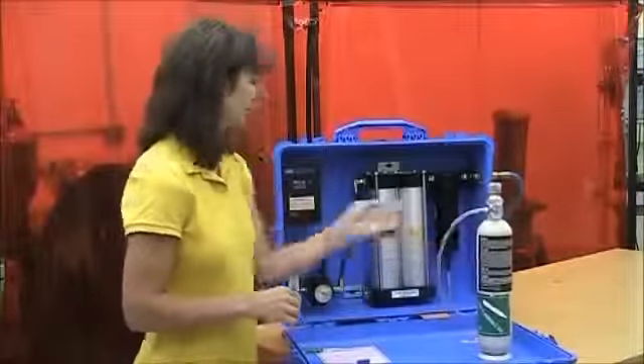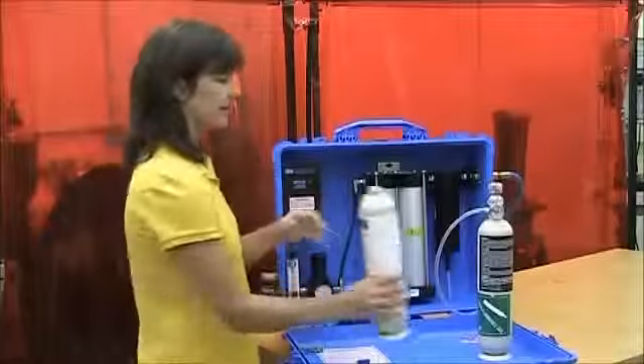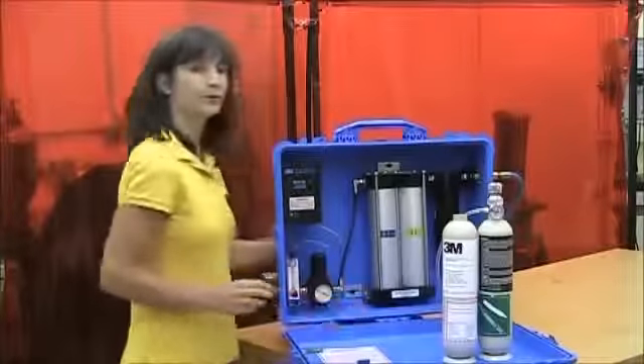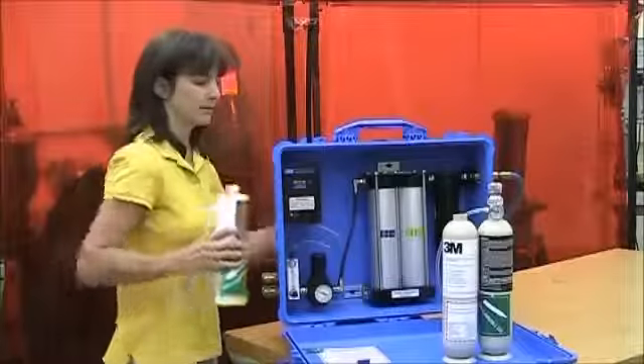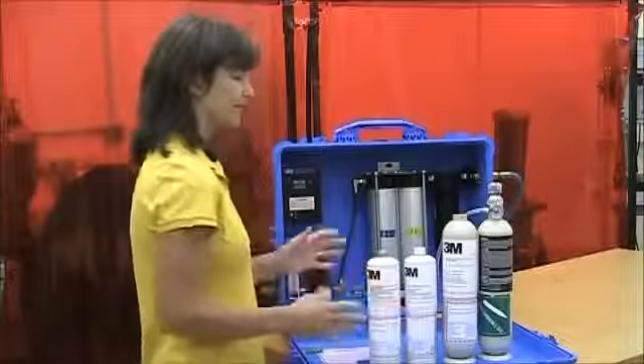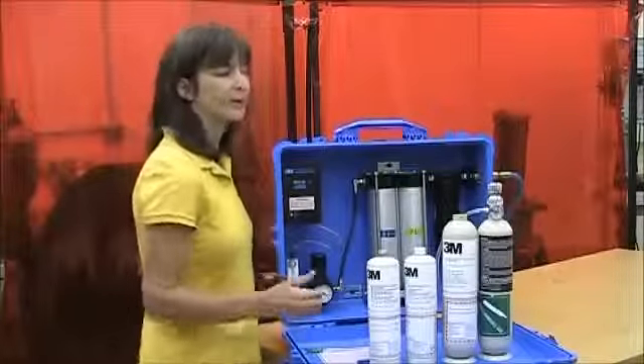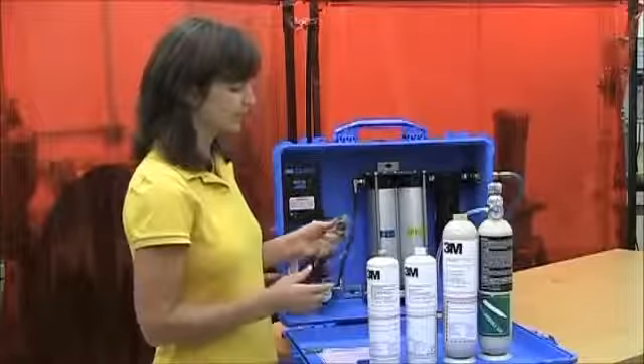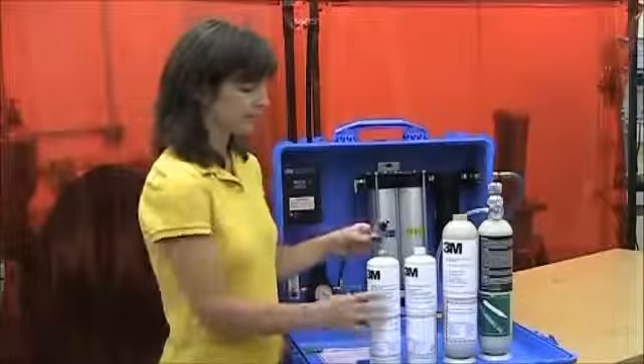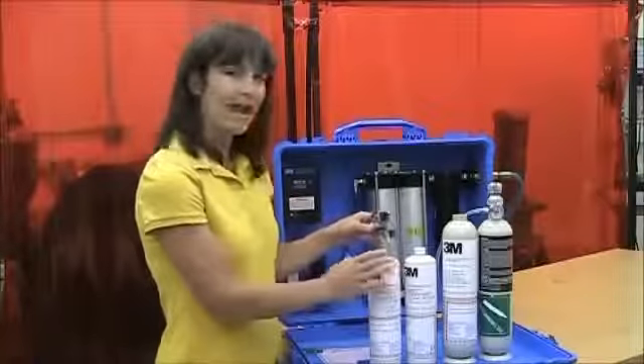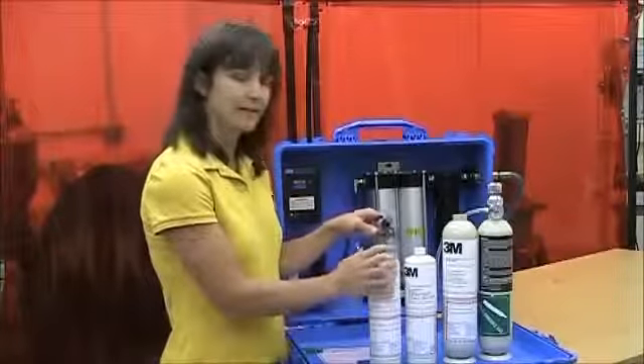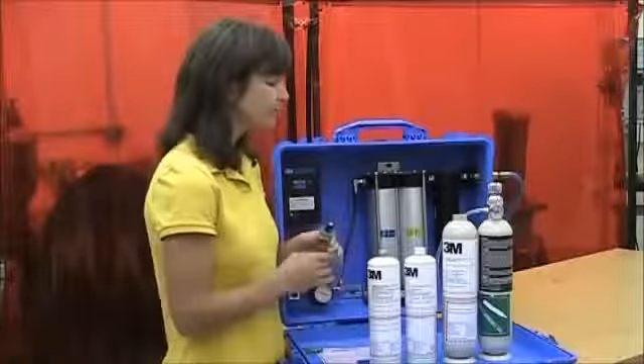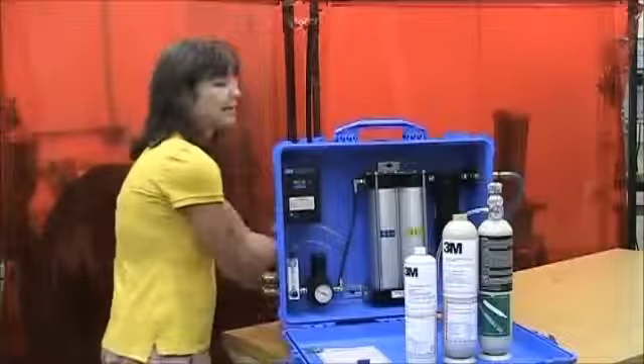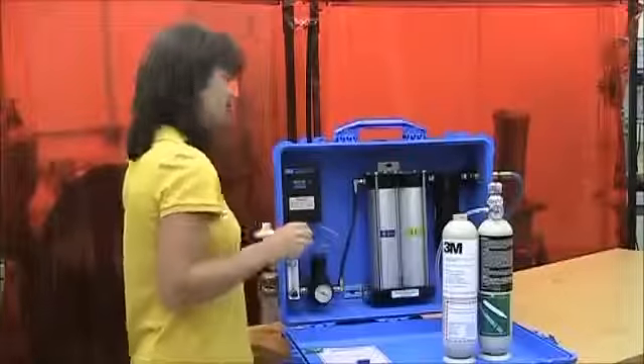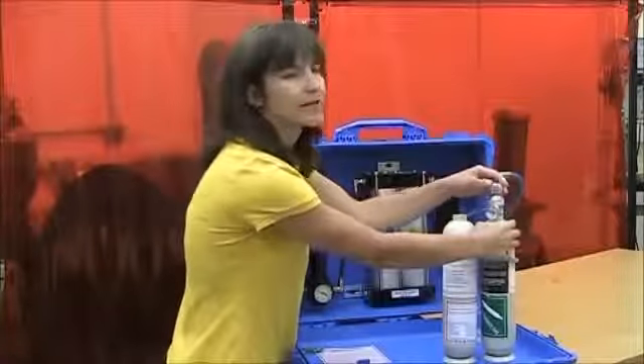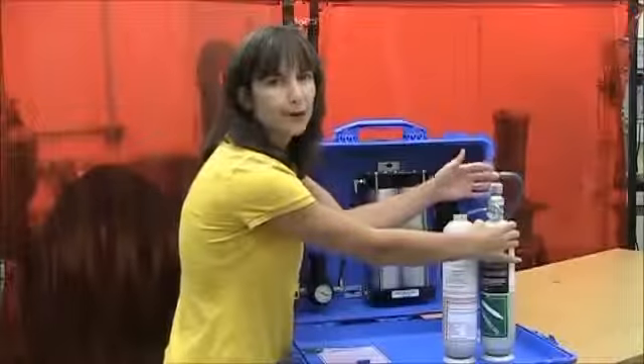We sell a large kit and a small kit. The large kit has bottles that are 103 liters. The small kit, the bottles are 17 liters. So aside from being able to get more calibrations out of the larger kit, the difference really is in the regulator. The regulator that comes with the small kit does not have an on and off, so once the regulator is attached to the bottle, air is flowing. For the large kit, the regulator has an on and off, so you can help conserve calibration gas by turning the flow off when you don't need it.